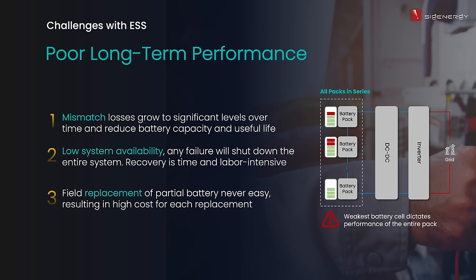Looking at the picture on screen, this is a conventional series-connected battery pack where if you have any failure or differences within the series string, you suffer the consequences. But since you're paralleled via the DC-DC converters, that's not a problem whatsoever.